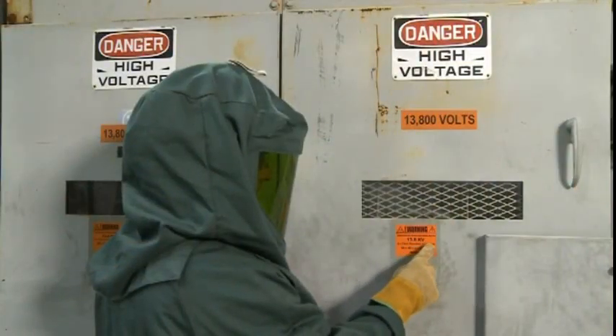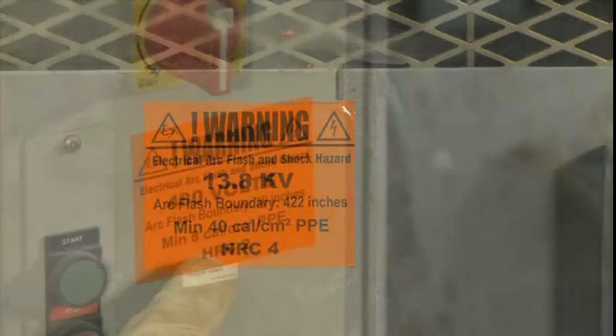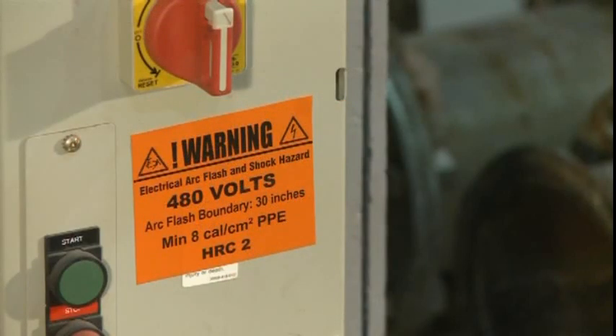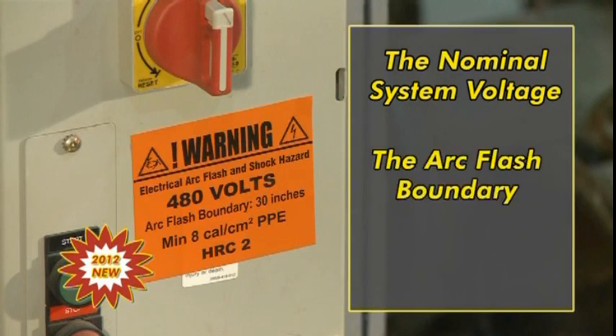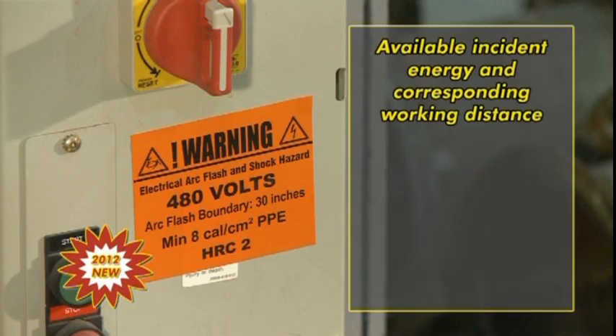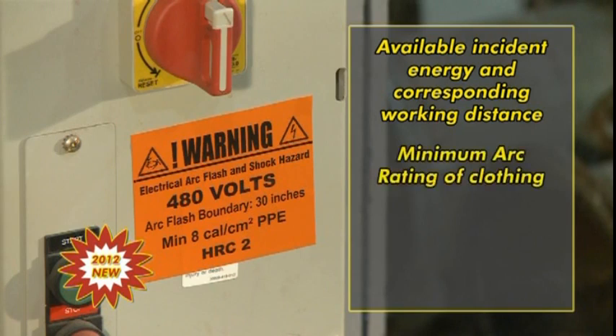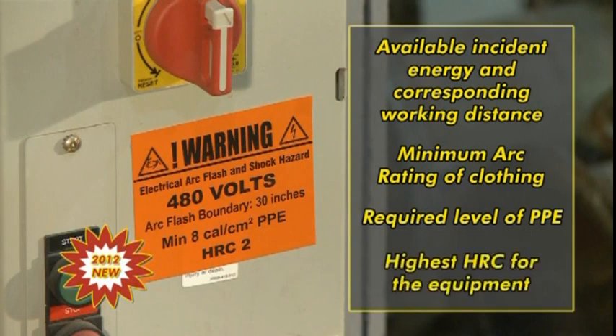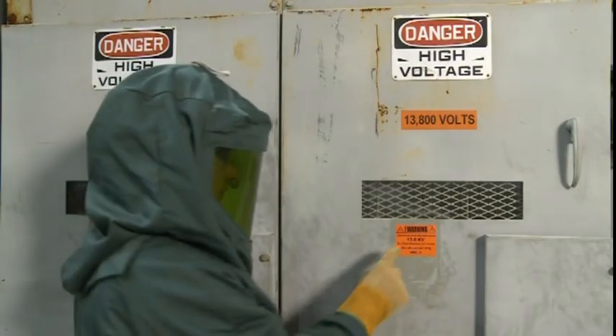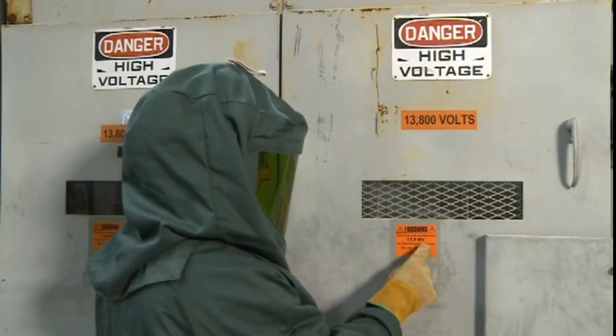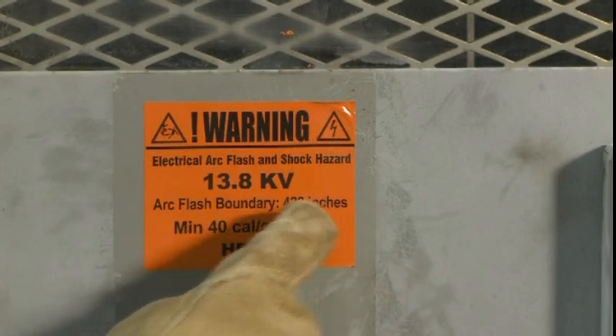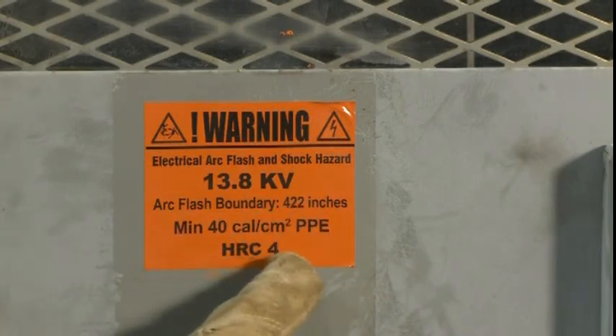A change to the 2012 NFPA 70E requires equipment be field labeled with the nominal system voltage, the arc flash boundary, and at least one of the following items: available incident energy and corresponding working distance, minimum arc rating of clothing, required level of PPE, or highest hazard risk category, or HRC, for the equipment. Having this critical information readily available makes the selection of proper arc-rated PPE easier for electrical workers.